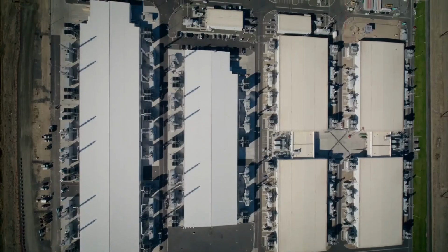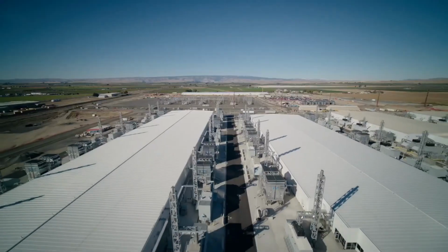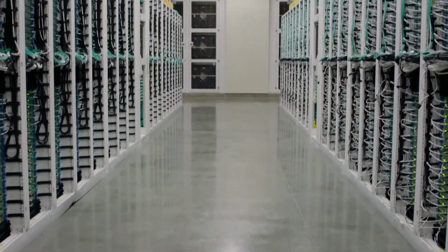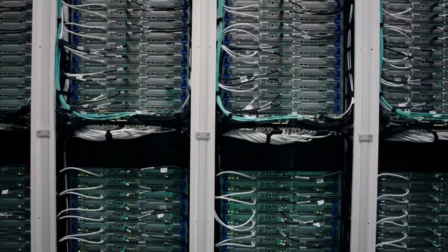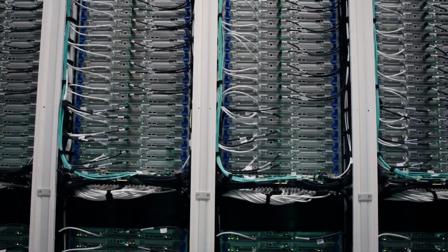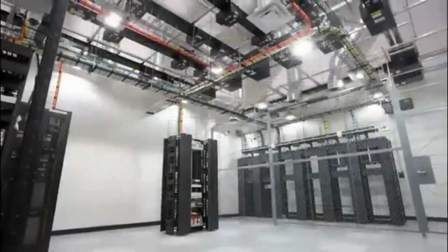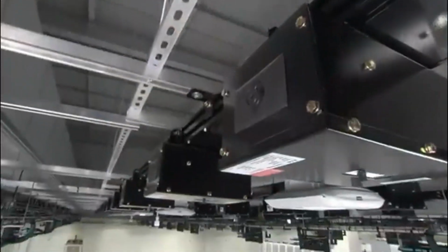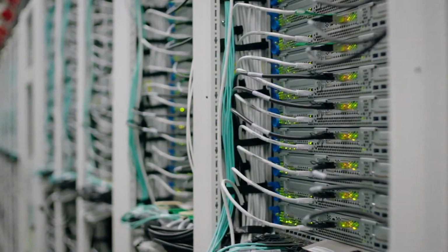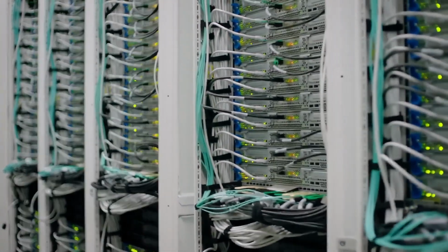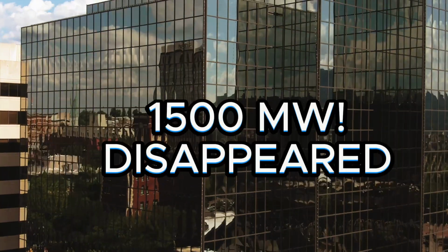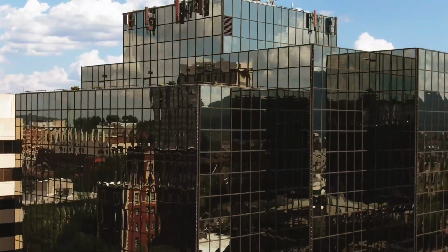There were 6 separate faults in under 90 seconds. This led to a series of short supply disturbances, lasting a matter of milliseconds before the system corrected itself. But it was enough to cause the data centers in the area to automatically switch to their backup UPS system as a precautionary measure, because data center loads are sensitive to voltage disturbances. Result, 1500 megawatt load disappeared off the grid almost instantly.